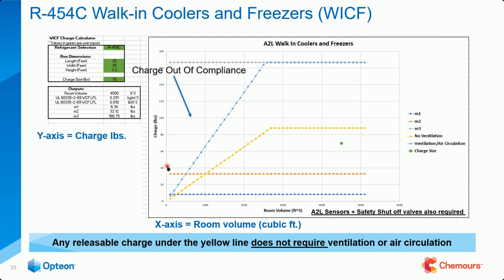So inside this blue area up here, anything over this way with this amount of charge and this amount of cubic feet right here is out of compliance. All right. If you move over here, you could be in compliance. But it depends on what you're going to need. But right here in this area, if you stop and think about it, this is a really low cubic feet. They're really talking about a very small area if you were inside that blue, the non-compliant space. And if you think about it, like I said, that's a very tiny room with a lot of charge. And the reason that is out of compliance is simply this: if you were to have a leak, the refrigerant in the small volume means the risk is higher, which would be a safety concern, obviously.